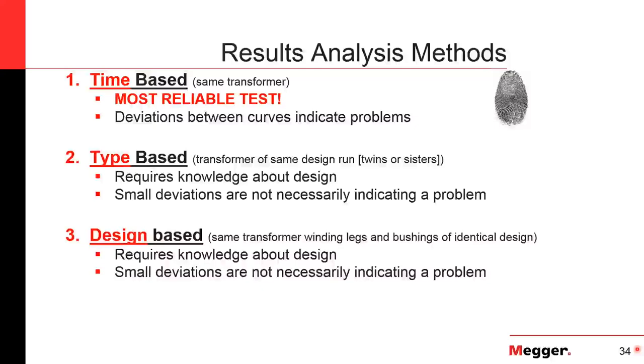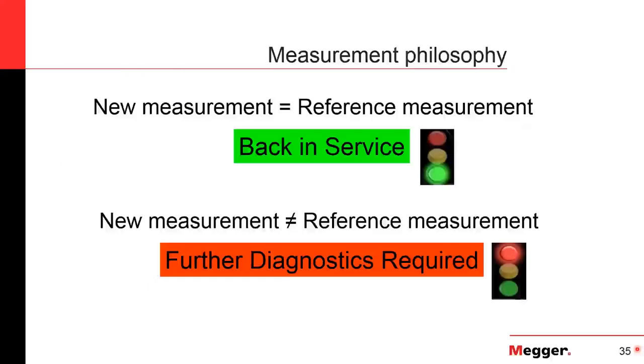Interpreting results is pretty simple in the basics. You take your new measurement and compare it to your reference. If they overlay and line up, there are no mechanical or physical changes inside that transformer — put it back in service. If your new measurement doesn't line up with your reference fingerprint, you know something physically or mechanically changed inside that transformer and further diagnostics are required.